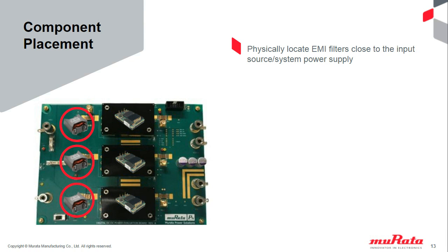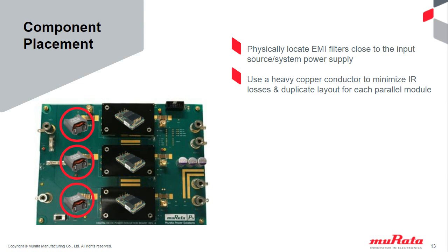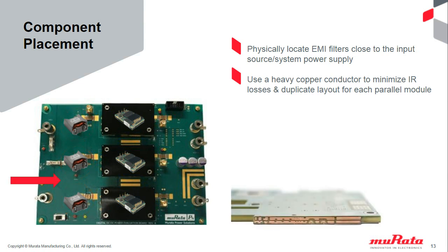You want to use heavy conductors that can carry the current. On the input side, the current is a lot lower because you have a 48-volt input, but on the output side, currents can come up very high very quickly. Again, under normal conditions, two modules each would be producing 25 amps, but in a failure condition, you're going to be producing 50 amps. You need to rate the copper that's carrying that current at 50 amps. Down below here, you can see a cross-section of a board where they're using heavy copper, interconnected copper layers, to carry that current.